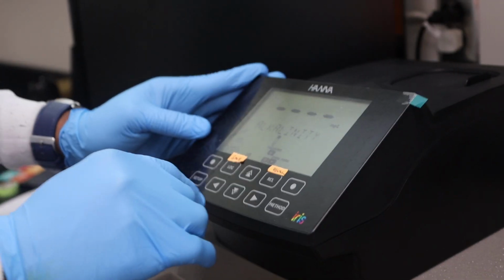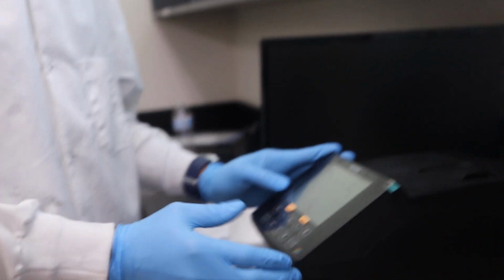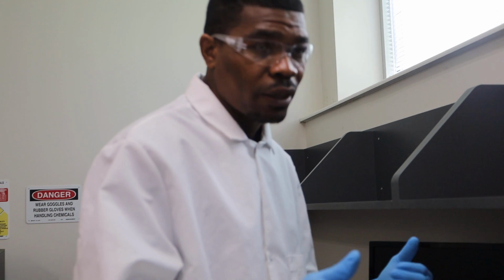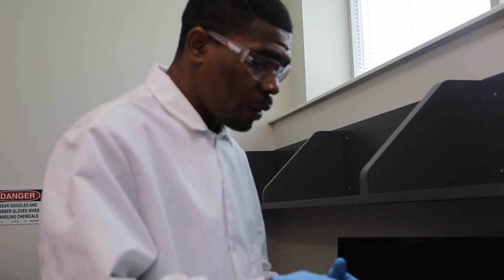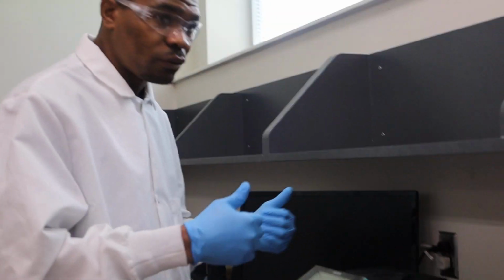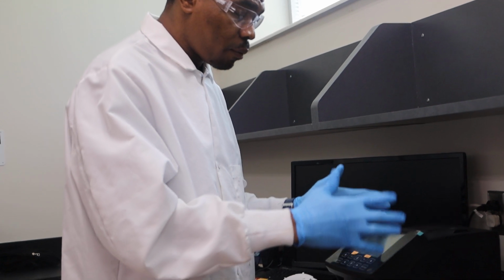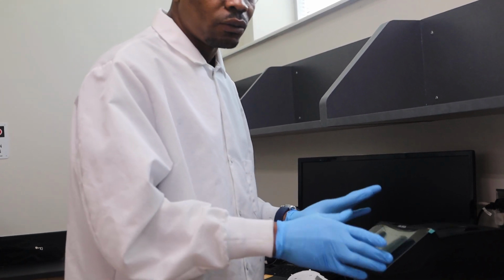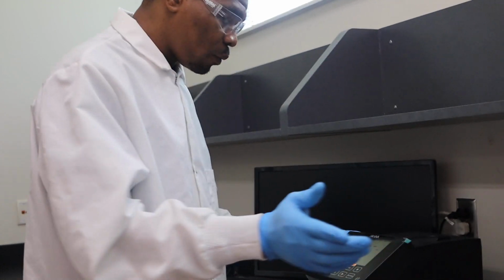So basically when you put it on, this is the interface you see. If you want to operate it, first you have to determine the kind of method you're going to use. The factory method is what brings on board the 98 parameters. But if you want to add some more parameters, you can also create your user method in addition to those methods.